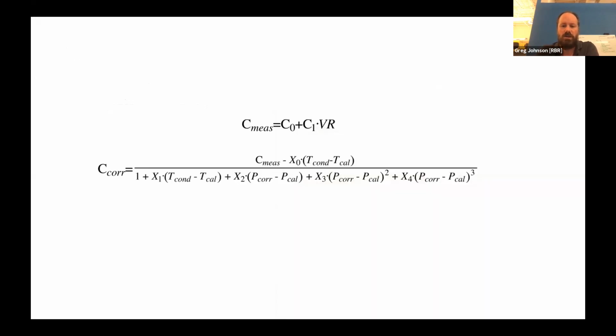And as you can see on the equation, we've also got usually a cubic to compensate for pressure. Why do we need to do that? The reason is that if you're familiar with an electrode cell, the cell constant is actually numerically just the ratio between the cross-sectional area and the length of the electrode cell glass tube, as you might see on a Seabird, for instance, with platinum electrodes.